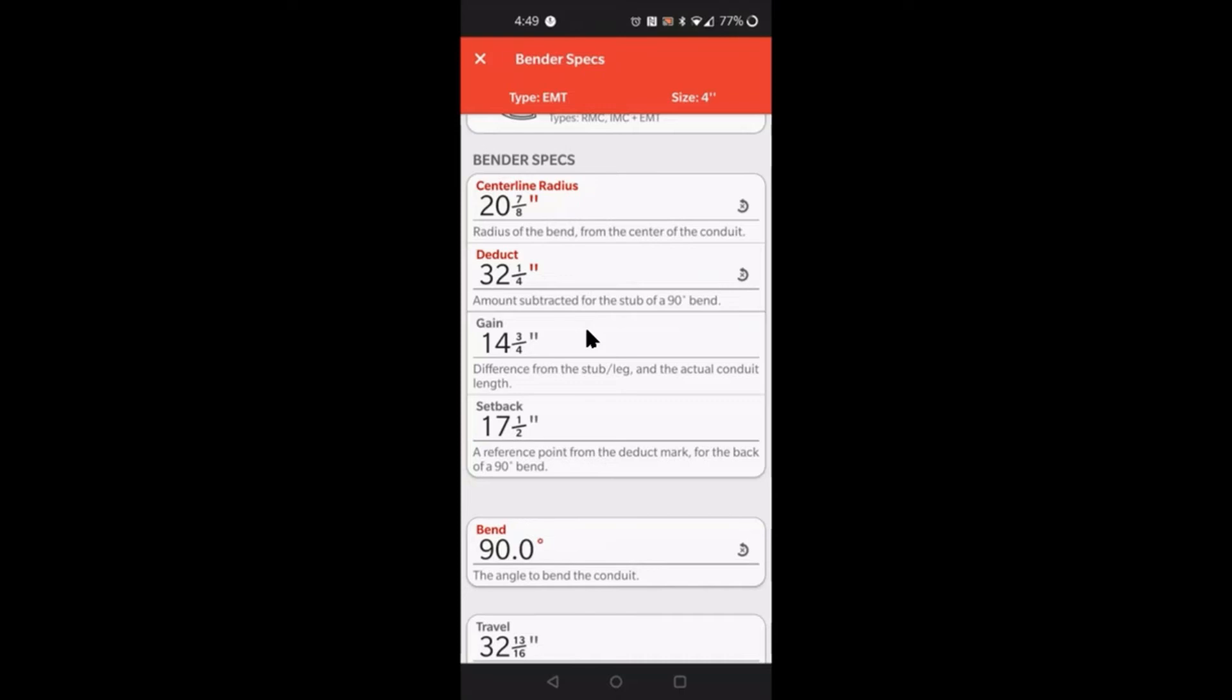But in a nutshell, basically this is the value that you want to deduct for every 90 that you bend on a length of conduit to find the total length for that conduit. Say if you wanted to make box sets or if you wanted to thread it, or just simply you want to know because you want to cut it to the exact size and then make your 90 degree bend, so you want to know how much you need. That's what the gain would be used for.